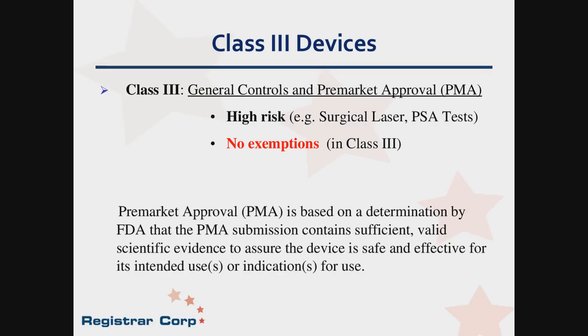Then we have the highest risk class, which is the class 3 devices. To market a class 3 device in the US, you are required to have what is called a pre-market approval. This is the only device that is really approved by the FDA, and this is the only time that you should use the word approval. It's only that device in class 3. The registration of your company or of a class 1 or class 2 device is not approved by the FDA. It's only a class 3 device. A class 3 device, for example, is a surgical laser or a PSA test. There are no exemptions on that one. You need to have that pre-market approval.